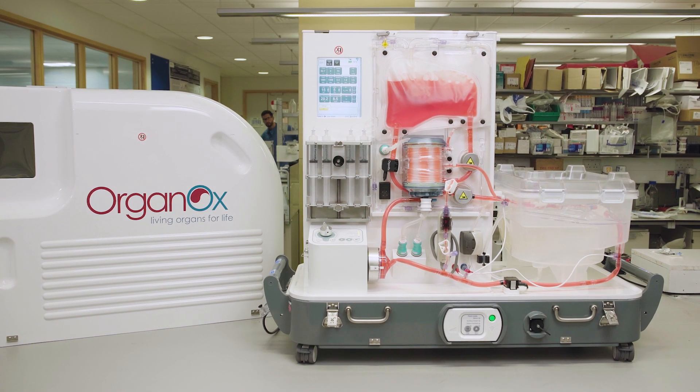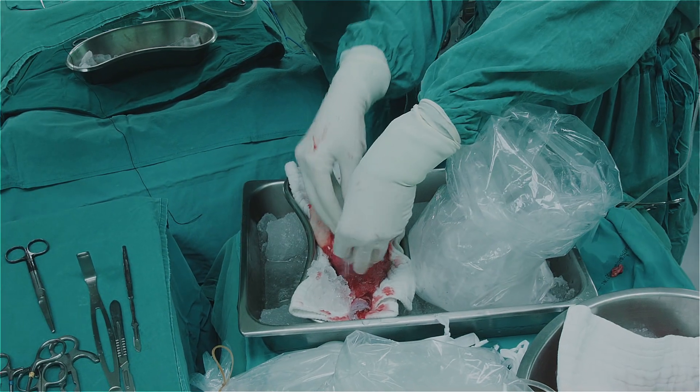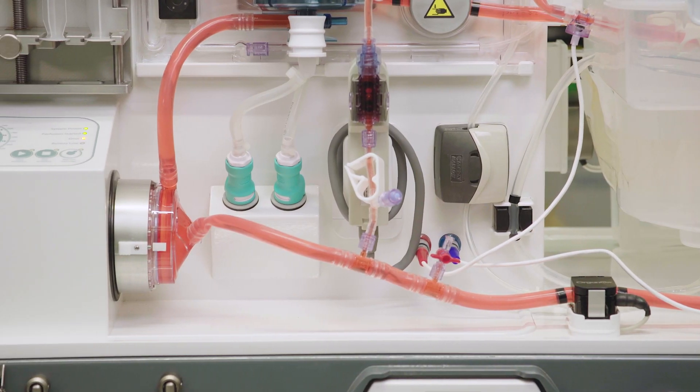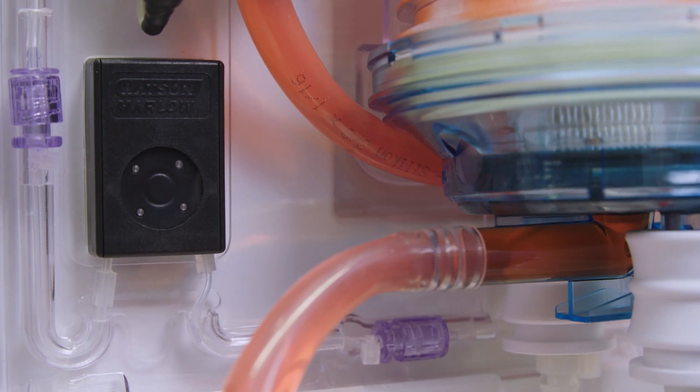The OrganOx metra is the world's first fully automated normothermic organ perfusion device. Traditional organ preservation involves cooling organs down to ice temperature. The problem is that cooling organs down isn't very good for them — there is damage. Normothermic means normal body temperature, and machine perfusion means we're actually pumping blood through the organ.